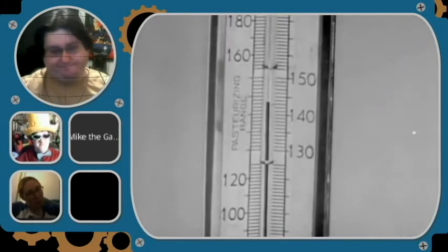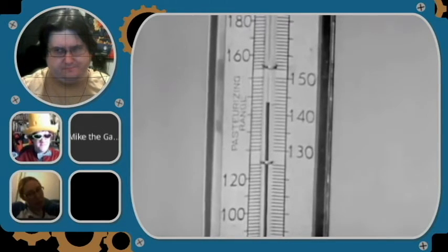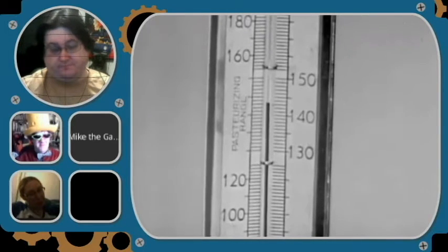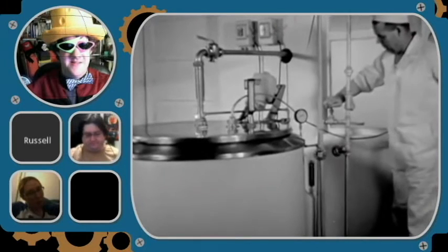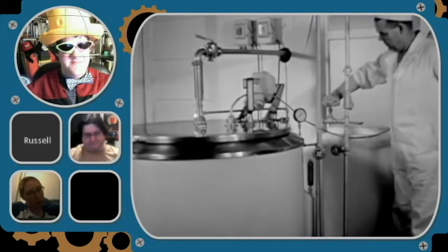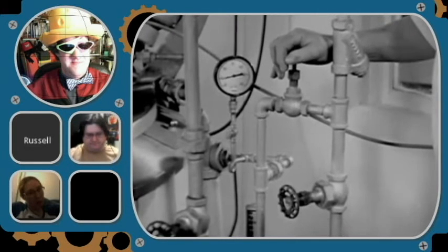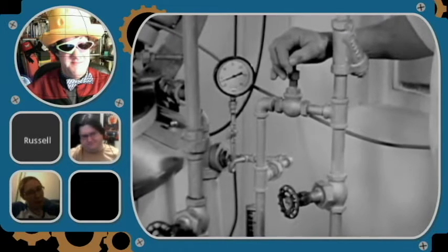Pasteurization begins when the temperature of the milk reaches 143 degrees, not one second before. This is the lowest temperature which, if held for 30 minutes, will kill all of the disease germs which might be in the milk. Well, most of them. The steam supply to the airspace heater is adjusted so that the airspace temperature is at least 148 degrees during the entire pasteurization holding time.